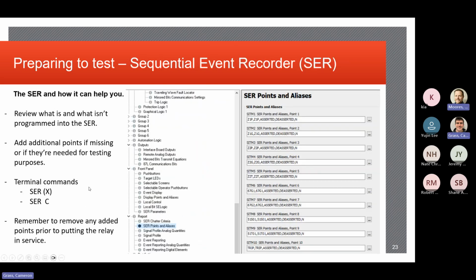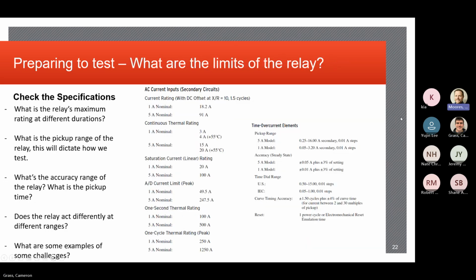Yeah, you could have a 5 amp nominal rated relay current input, but you might have a 45 amp instantaneous test point that you need to test. So that's 9 times the nominal, continuous rating of the relay. But you've got to figure out, obviously, the relay is designed to see that for very short periods of time.